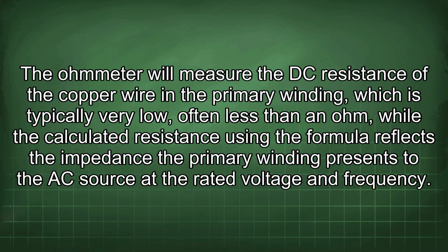The ohmmeter will measure the DC resistance of the copper wire in the primary winding, which is typically very low, often less than an ohm, while the calculated resistance using the formula reflects the impedance the primary winding presents to the AC source at the rated voltage and frequency.